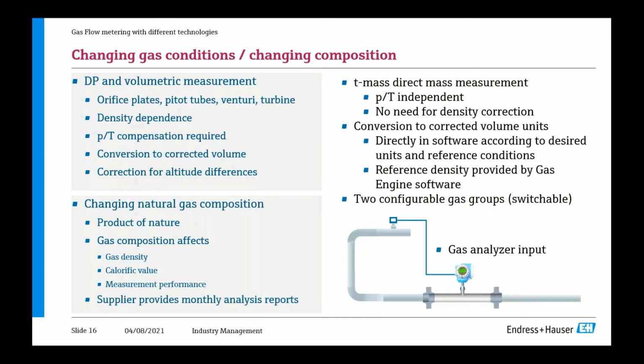Because natural gas is a product of nature, it does have a tendency to change over time. Due to that change, it can have an effect on the gas's density and also on its calorific value. So certain types of measurements, for example DP volumetric types of measurements, are influenced by this, because they are density dependent. The T-mass device, like I said before, is a direct mass measurement. There's no need for pressure and temperature compensation, no need for density correction. The software of T-mass also provides the reference density, and this again can be used to convert from mass into corrected volume units. Also, there is the ability to input a gas analyzer to the T-mass for compensating dynamically for changes in the gas composition.